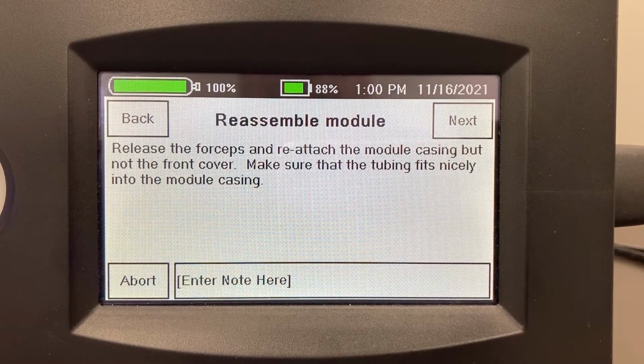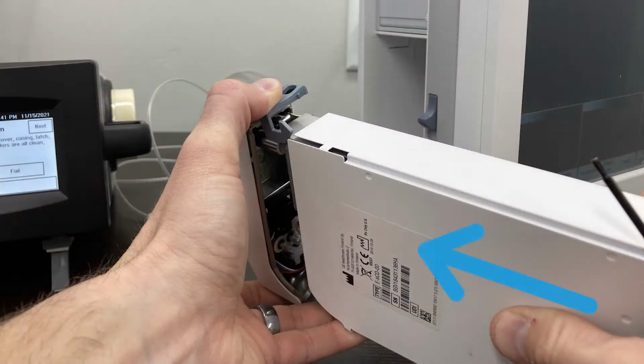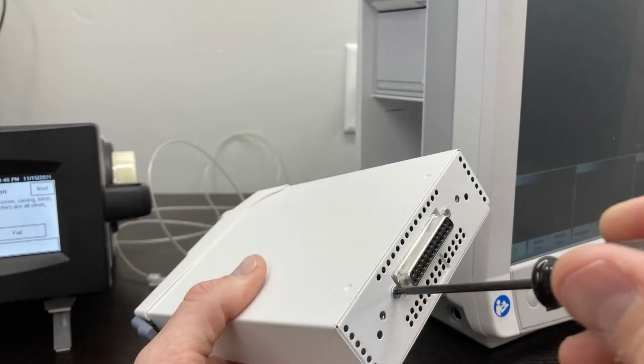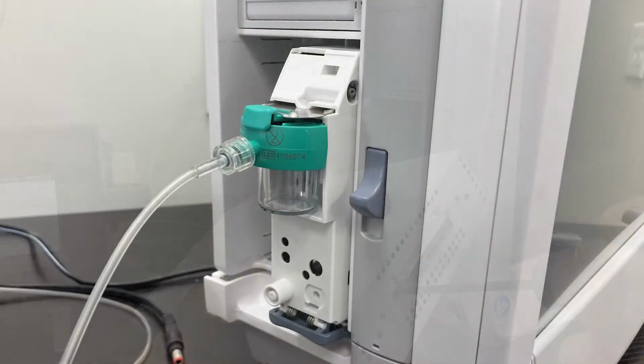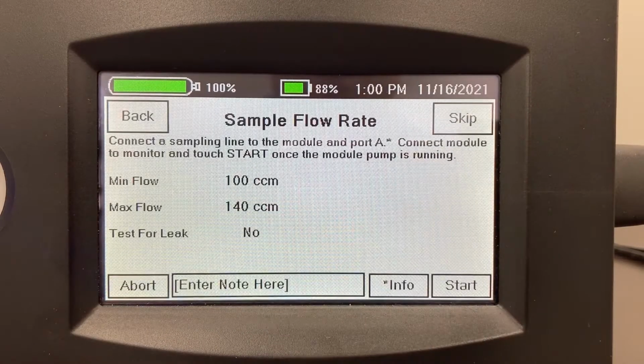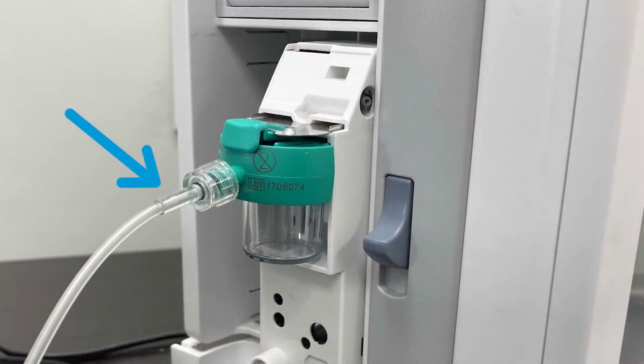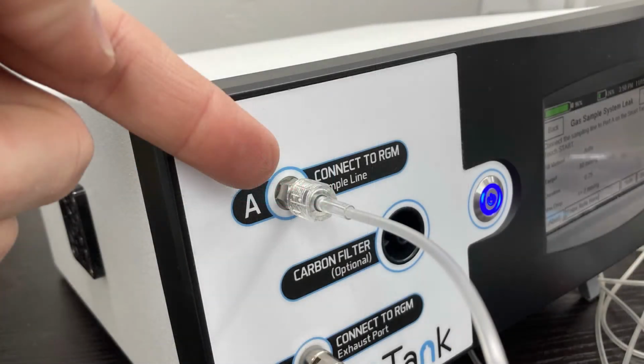Next, we will reassemble the casing. Now this is just the back sheet metal casing and not the front cover. And then we'll install the module back into the monitor. And the module will start running. When you hear the pump running, you can connect the sample line of the module you're testing to port A on the SmartTank.